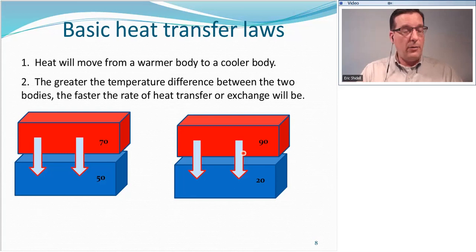Now, I can also have a boiler that has a supply water temperature of 180 degrees, and a return water temperature of 176 degrees. This gives me a temperature difference of 4. This means something very different to me than it does when the temperature difference is 20. This has a lot to do with the rate of heat transfer and the rate of heat exchange. And as we move forward in our course, I'll explain that concept in much greater detail. But for right now, I just want you to be aware that measuring temperatures is very, very important.